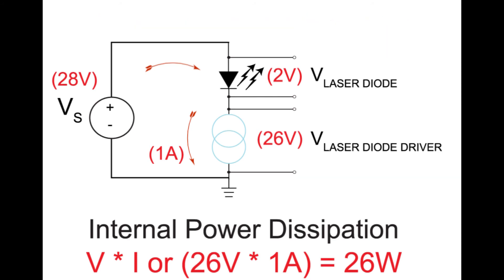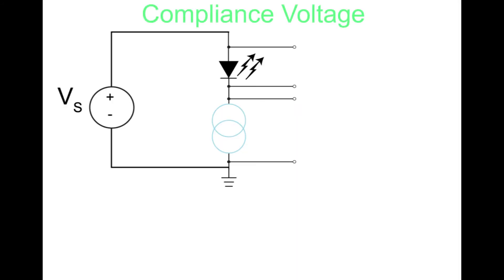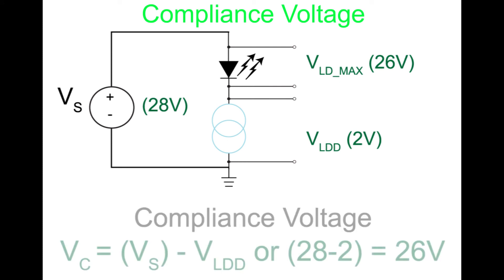Instruments have built-in SOA protection. Compliance voltage is the power supply voltage minus this internal voltage drop across the laser diode driver. It is the maximum voltage that can be delivered to the laser diode. It is typically specified at full current.